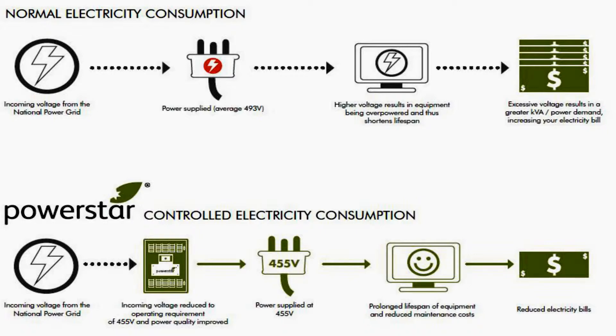What we do is verify the site voltage on the primary side and optimize the voltage on the secondary side. This voltage on a 480V nominal site is optimized typically at 460V, which is the voltage motors are designed to run most efficiently at.